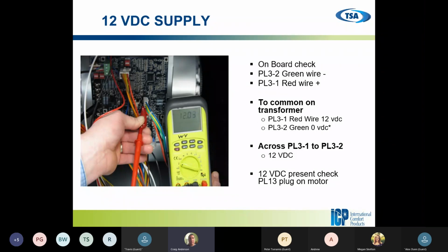We also want to check our ground. We do know it's a ground, but we want to make sure that we're not getting voltage on that. If we're getting voltage on that, then maybe we have something back feeding through that motor or somewhere else. So always check your grounds as well when you're checking your wires. And then now we want to check between our red and our green to see if we have our 12 volts present there as well. And like I said, it should not be fluctuating.